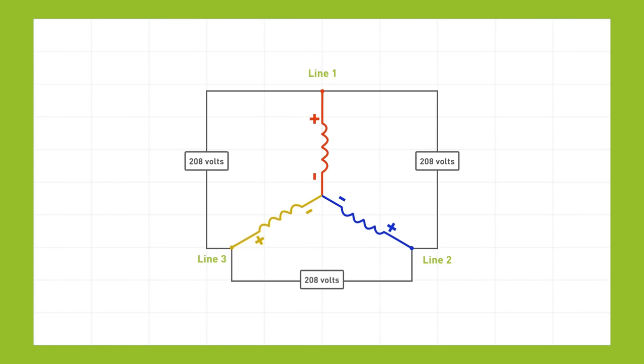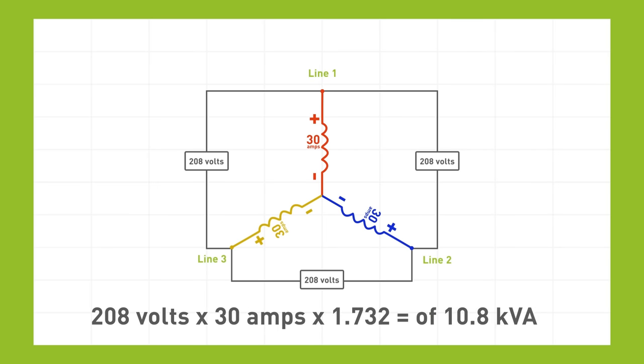If the wire is capable of delivering 30 amps, then the power that's being delivered is 208 volts times 30 amps times 1.732 for total power available of 10.8 kilovolt amps.